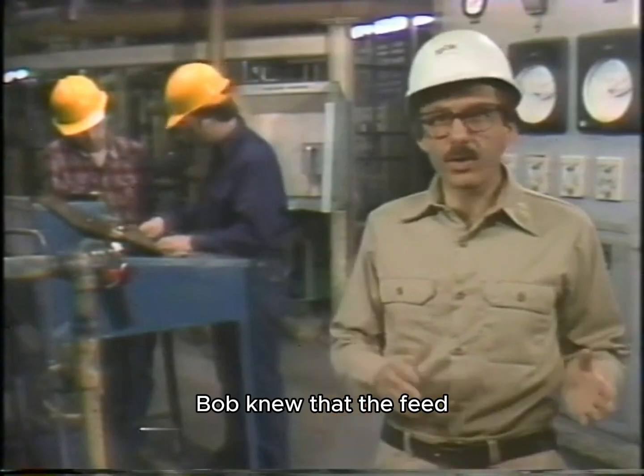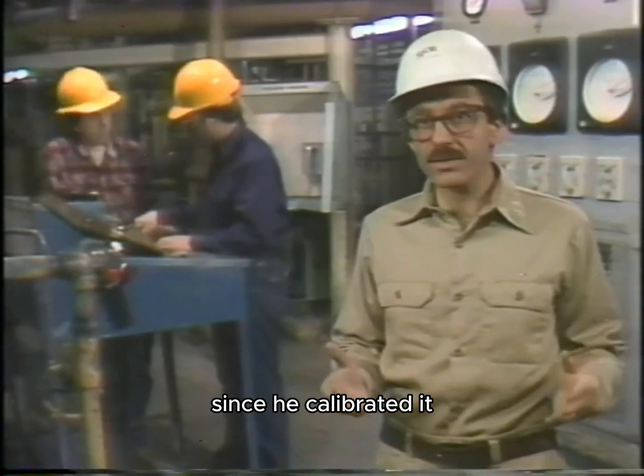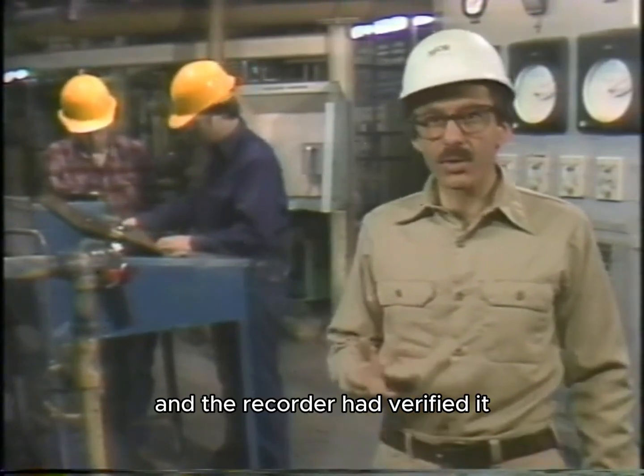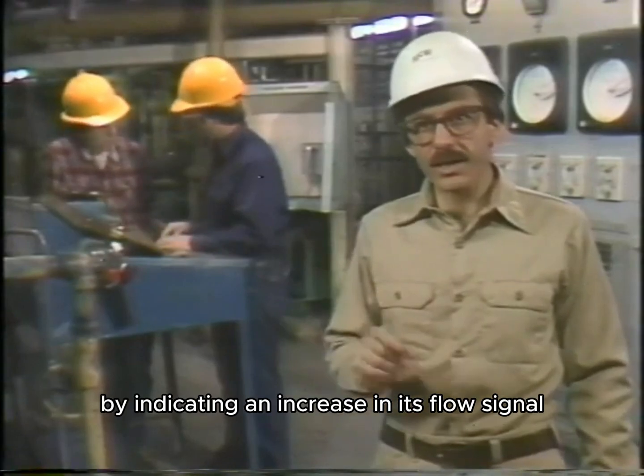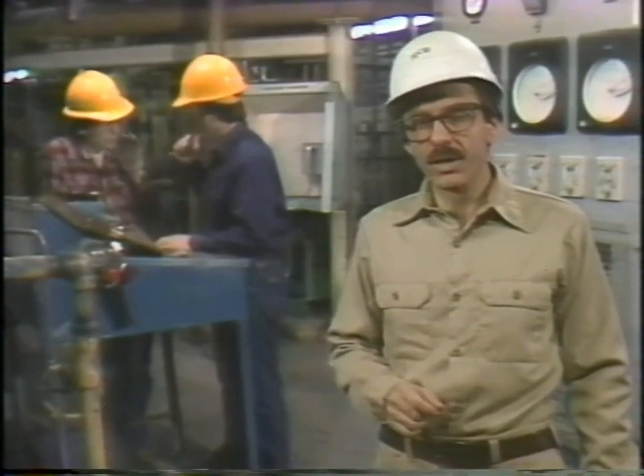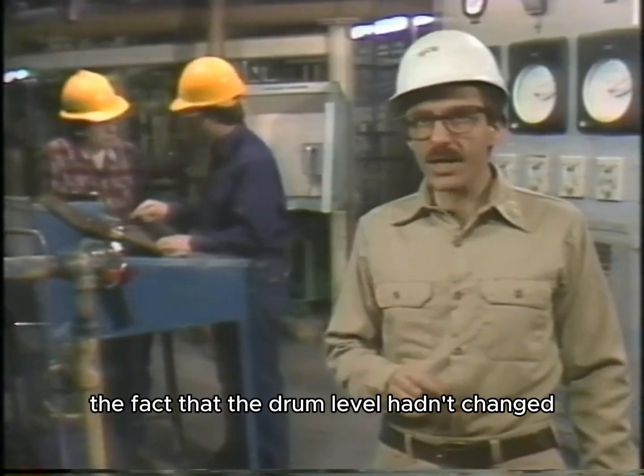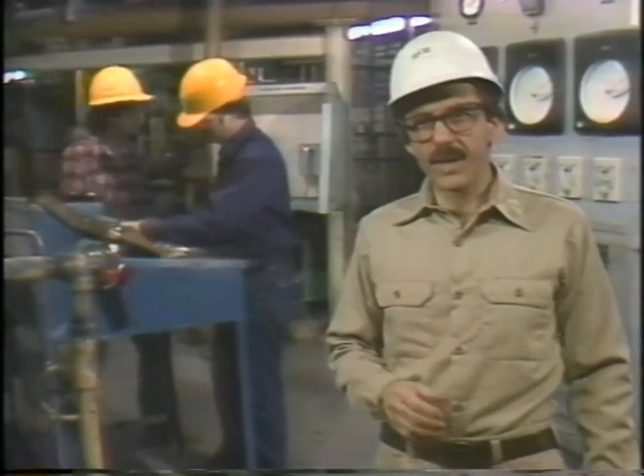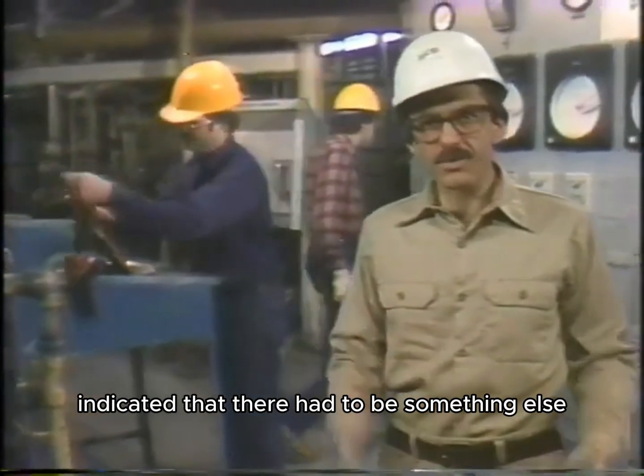Bob knew that the feedwater flow transmitter had to be okay since he'd calibrated it, and the recorder had verified it by indicating an increase in its flow signal. But the fact that the drum level hadn't changed with the system in automatic indicated that there had to be something else wrong with the system.